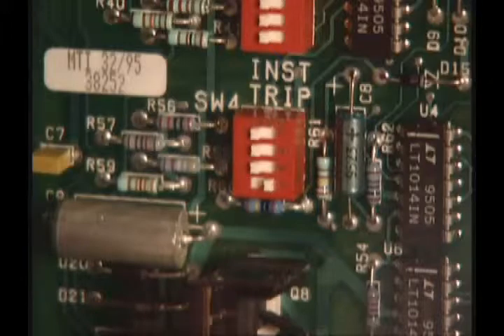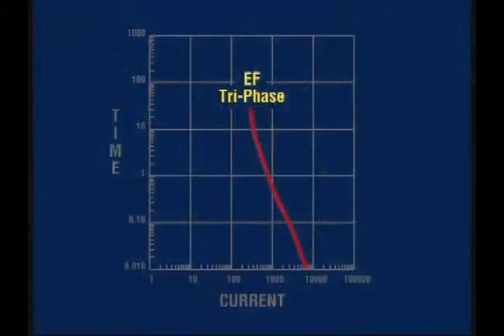Instantaneous trip bypasses the normal time delay characteristics to provide instantaneous tripping in response to high magnitude faults. With instantaneous trip, fault duration is reduced and coordination with source side protection is extended to provide improved system coordination and selective zoning. A separate dip switch bank on the control activates and programs the instantaneous trip feature. A multiplier is applied to each phase minimum trip setting to set instantaneous trip current values. When the fault current exceeds that value, the control will trip immediately, eliminating any intentional time delay. For faults below the instantaneous trip level, the control operates according to normal TCC characteristics.